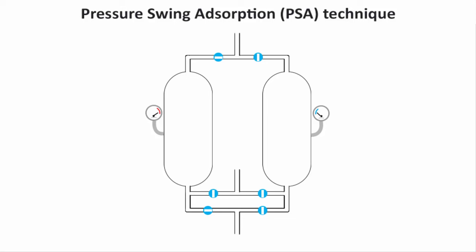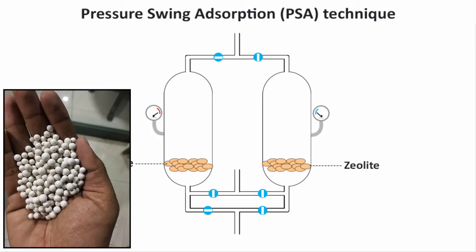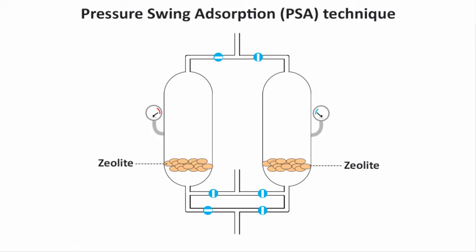Now let's see how PSA technology works. You need two pressurized tanks or vessels. At the bed level of these two tanks, zeolite pellets are placed to act as an adsorbent. The process starts by blowing dry compressed air through a valve into the first vessel, where the pressure inside is built to reach around 5 to 10 bar — anywhere around 70 to 150 psi.